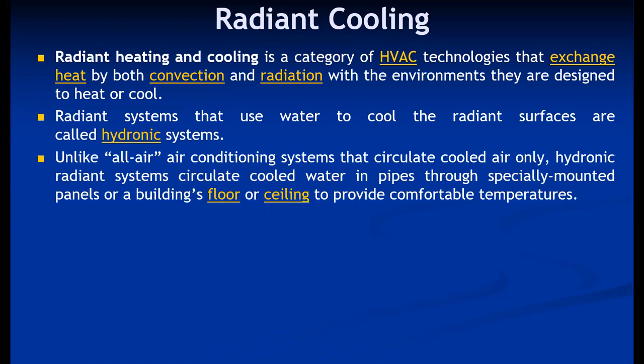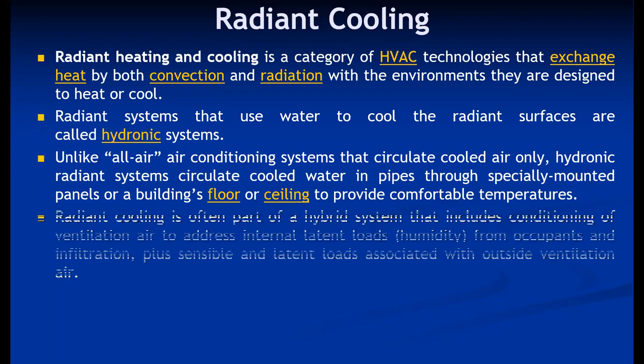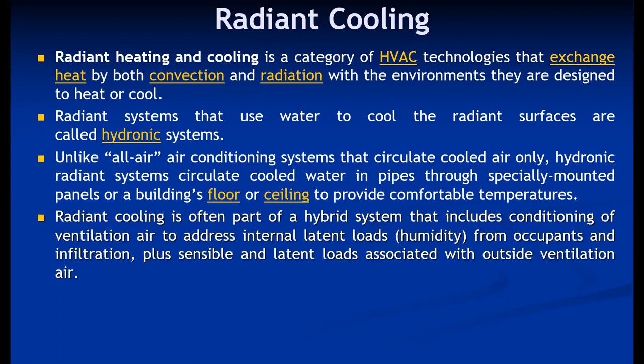Unlike all-air conditioning systems that circulate cooled air only, hydronic radiant systems circulate cooled water in pipes through specially mounted panels or a building's floor or ceiling to provide comfortable temperatures. Radiant cooling is often part of a hybrid system that includes conditioning of ventilation air to address internal latent loads, especially humidity from occupants and infiltration, plus sensible and latent loads associated with the outside ventilation load.